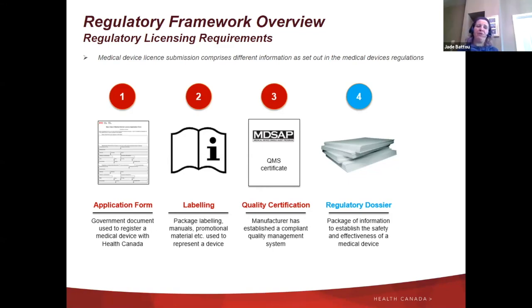In terms of the regulatory licensing process, manufacturers are accountable to supply all these documents to have their devices authorized in the Canadian market. This pathway is applicable to class 2, 3, and 4 medical devices. They supply an application form, a medical device license application form. They also have to supply medical device labeling, where we have to find the medical device name, manufacturer information, a device identifier, and the indication for use, which is also the most important part of the device label.